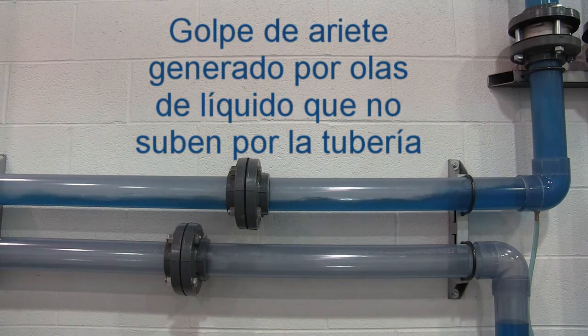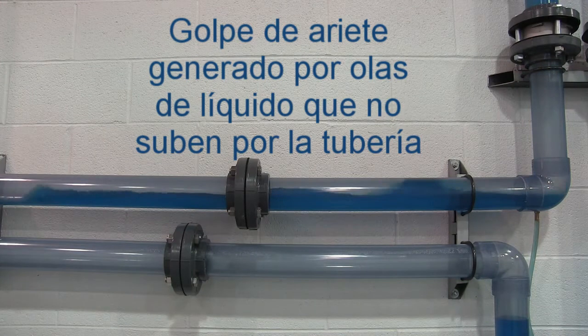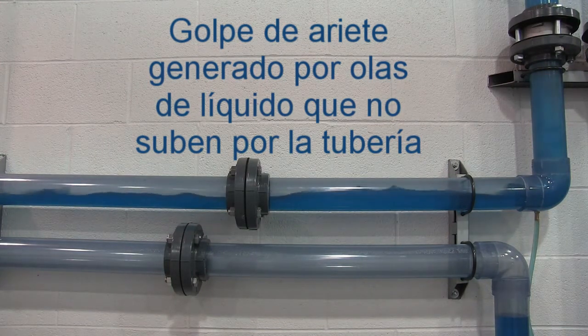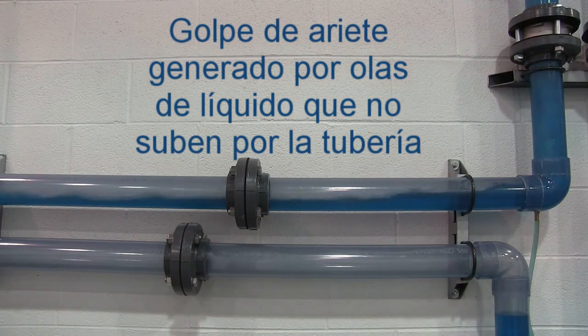Two scenarios are examined. First is a commonly seen piping installation of flashing condensate with a vertical rise. Wave action can be seen in the top pipe, caused by high-velocity steam moving over the surface of the liquid, gradually forming waves within the pipe.